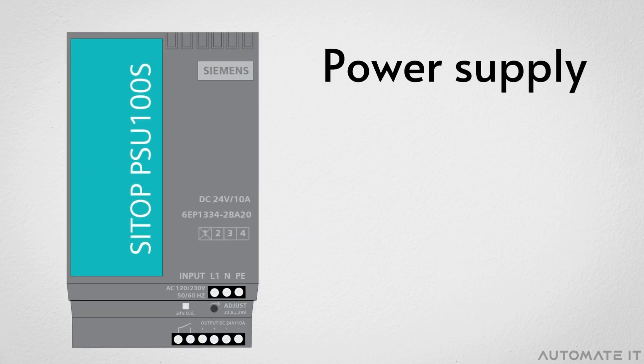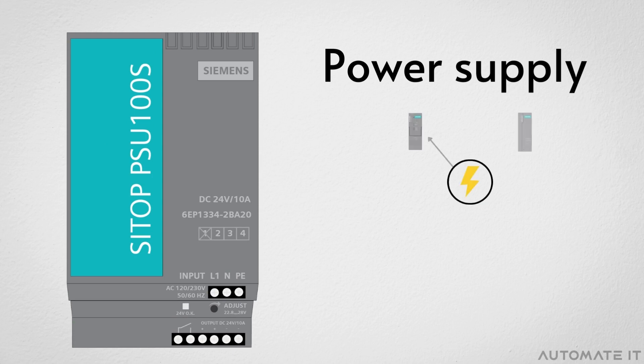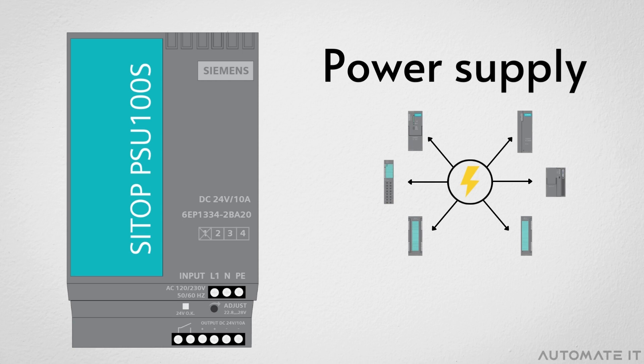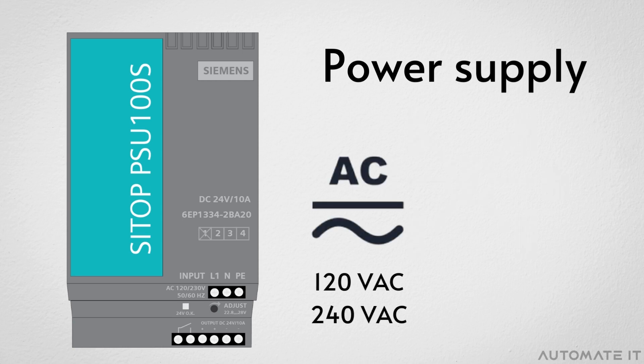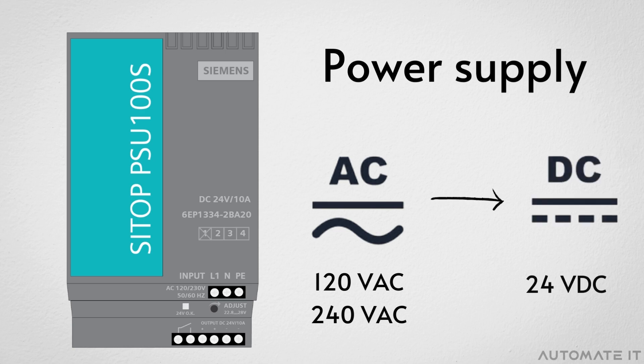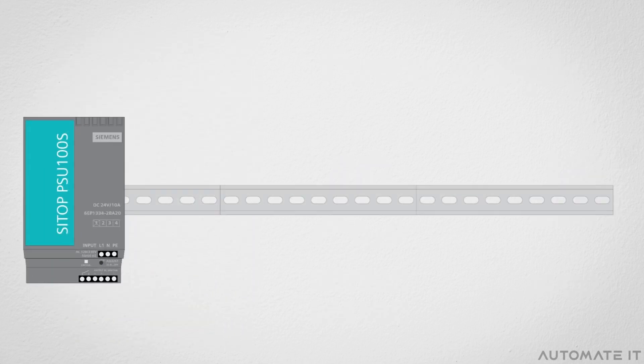First, let's take a look at the power supply. It is responsible for distributing electrical energy to the other components of the rack. In general, it converts 120 or 240 volt AC into 24 volt DC. On the rack, it is located in the first position.